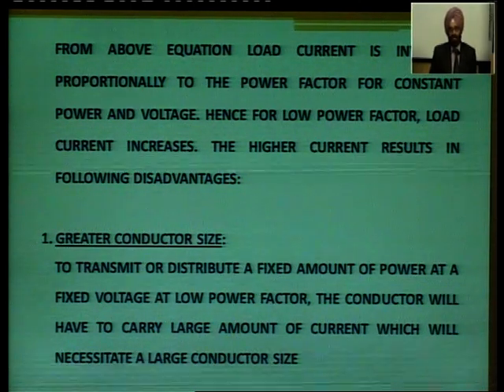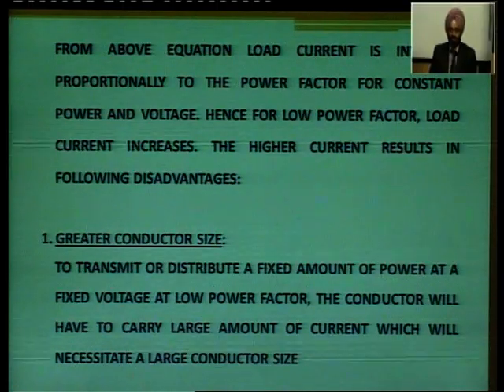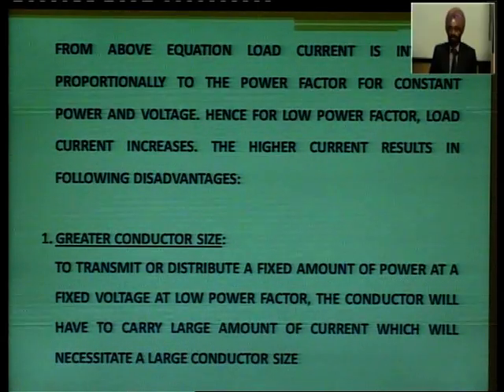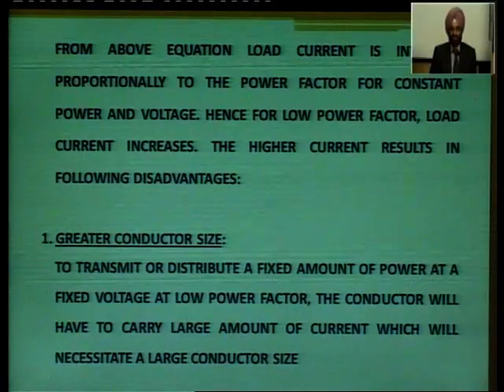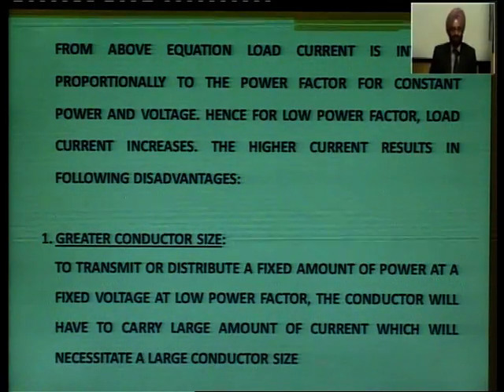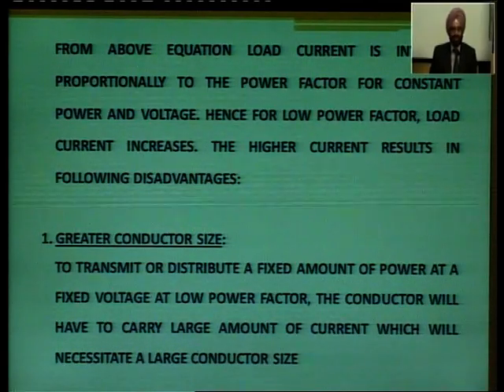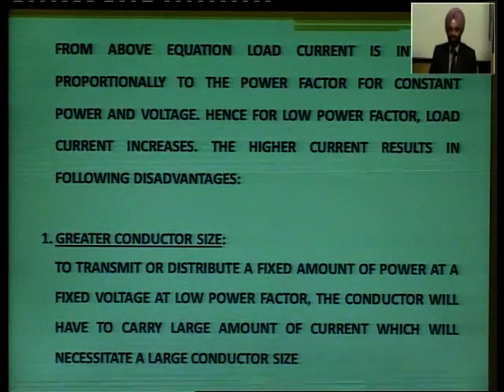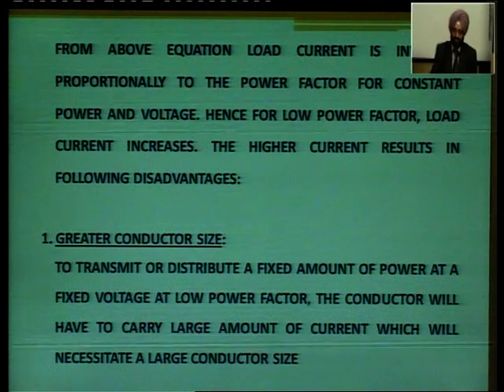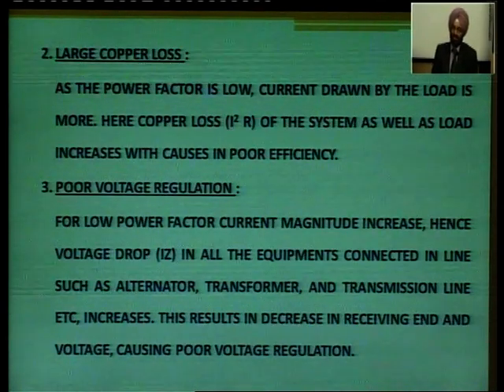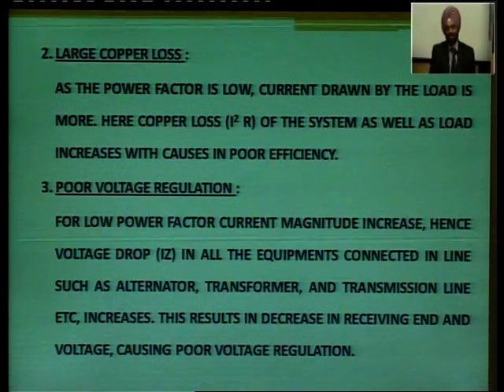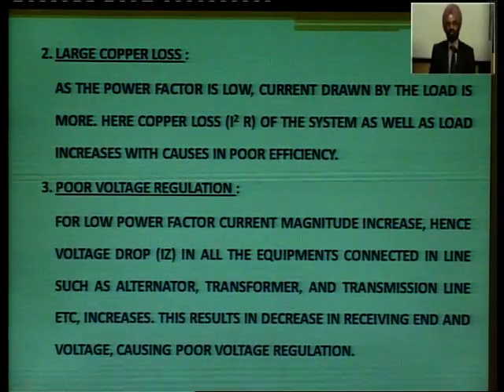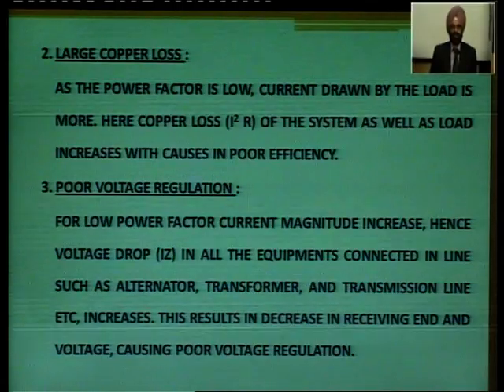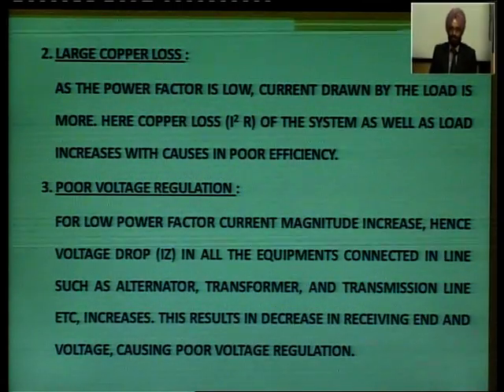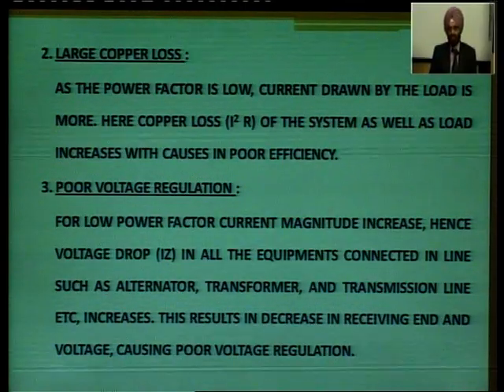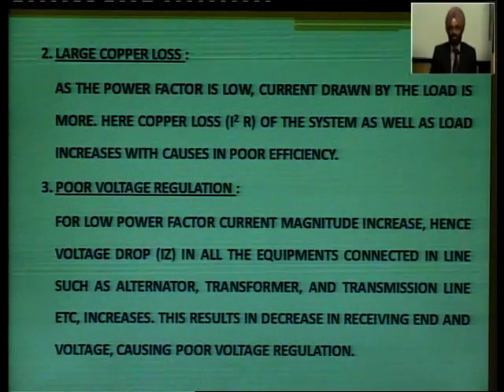I have already told you, the lower the power factor, the higher the current. If the current is more, then some disadvantages are created in our power system. First of all, if we have more current, we require a greater conductor size, so we have to spend more money to buy the conductor for the same load. Next, we have larger copper losses. Definitely, if we have a conductor, then the resistance of that conductor is fixed. If more current is flowing through that line, the copper losses go up: if the current is doubled, the copper losses become 4 times. So this is one of the biggest disadvantages of a lower power factor.